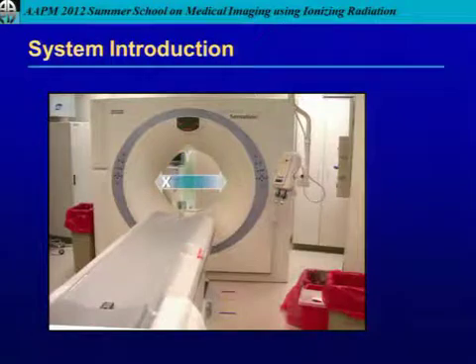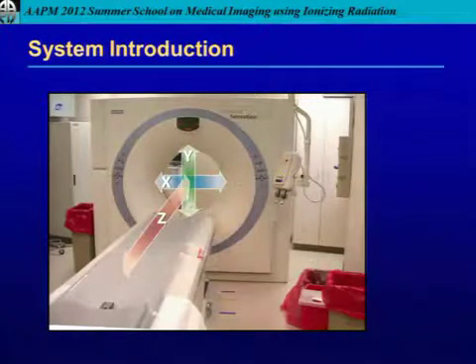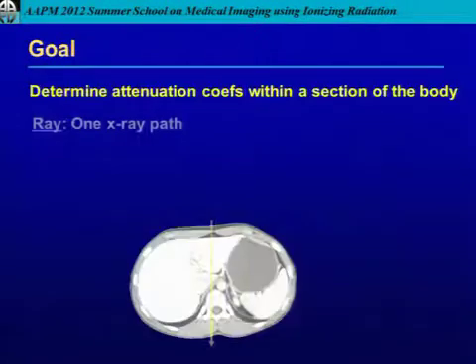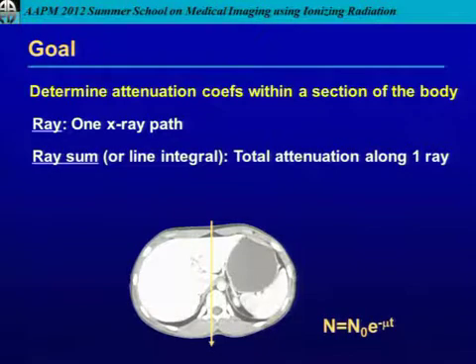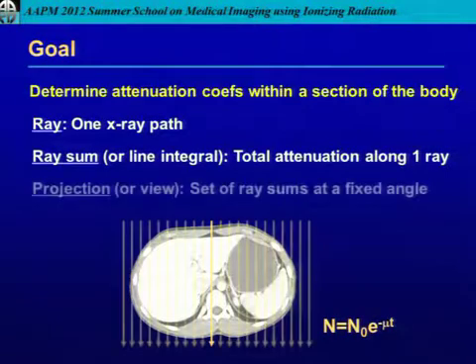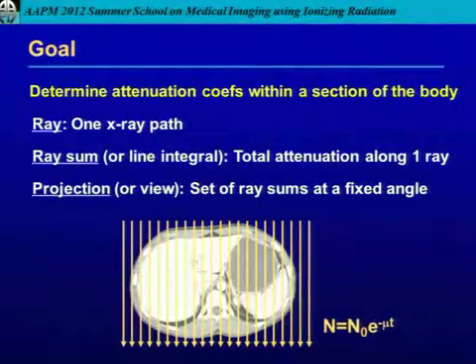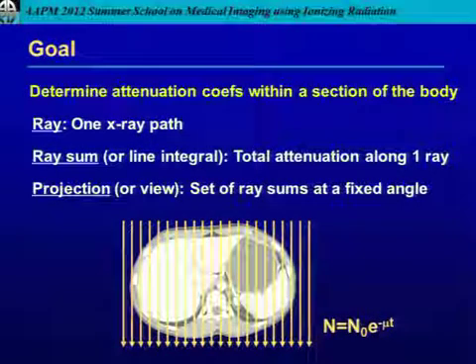Here's our coordinate system: the XY plane is our scan plane, and the Z axis runs along the longitudinal direction — the direction of the patient or the table. We need to define a few things. Our goal is to determine attenuation coefficients within a section of the body. A ray is one X-ray path, a ray sum or line integral is the total attenuation along one ray, and a projection or view is a set of ray sums at a fixed angle.